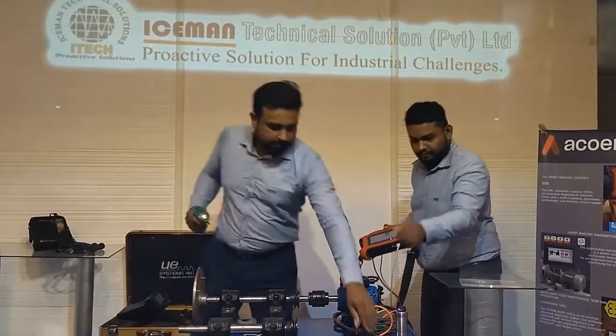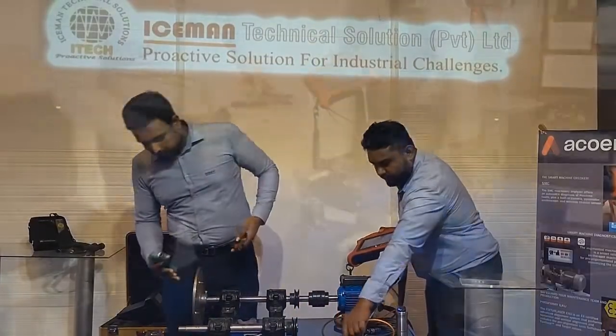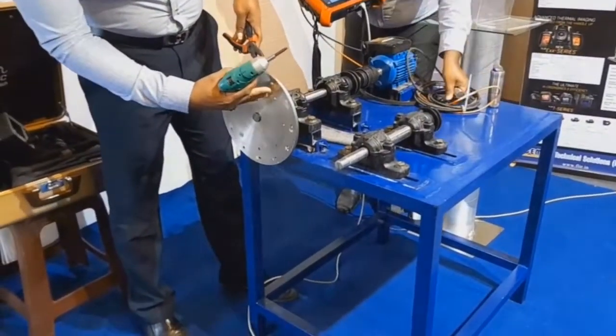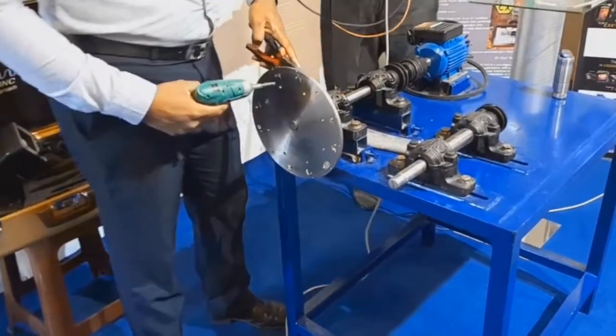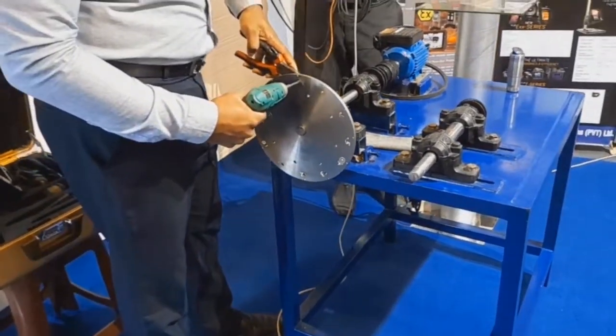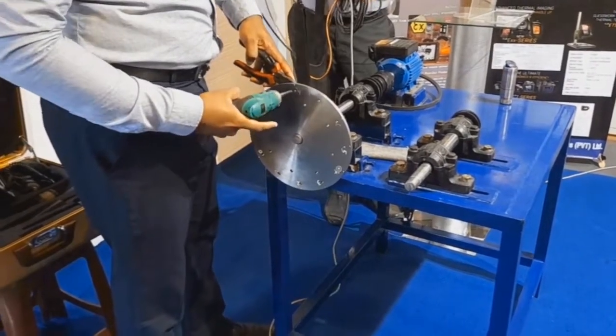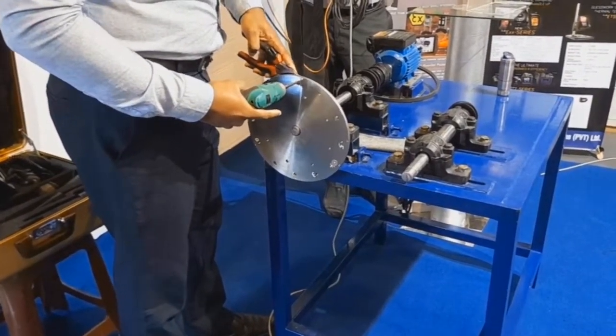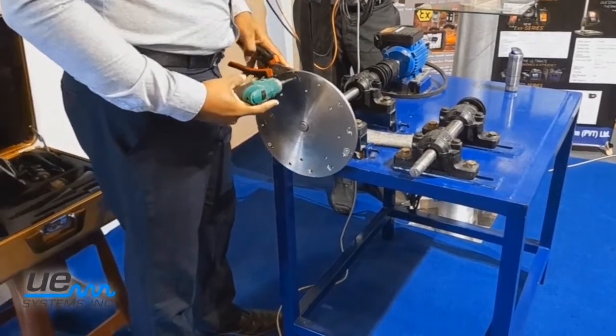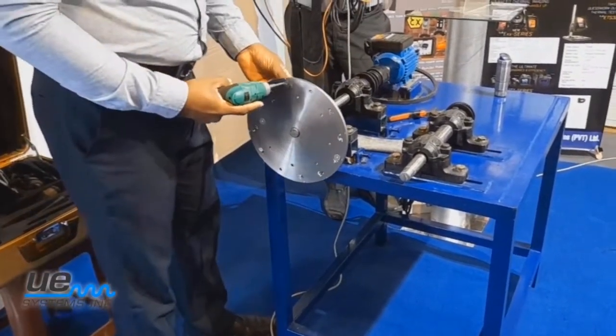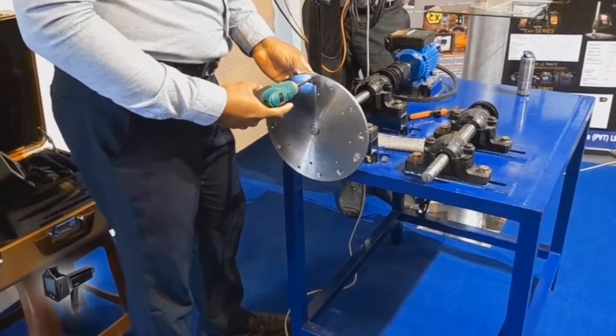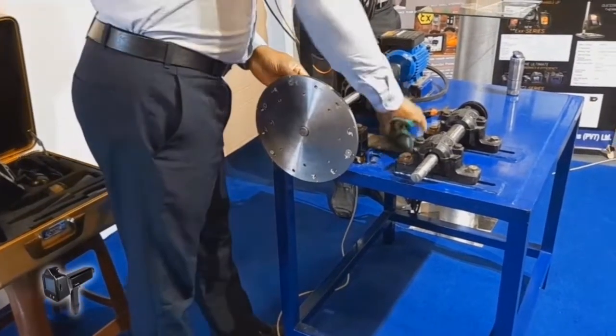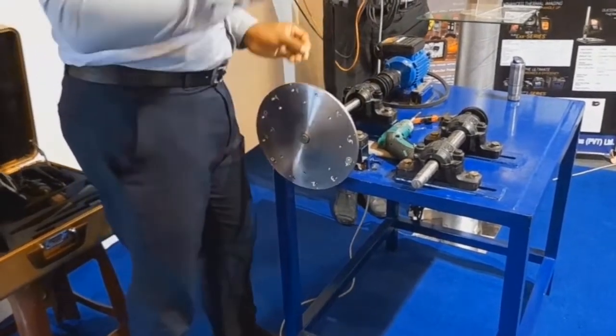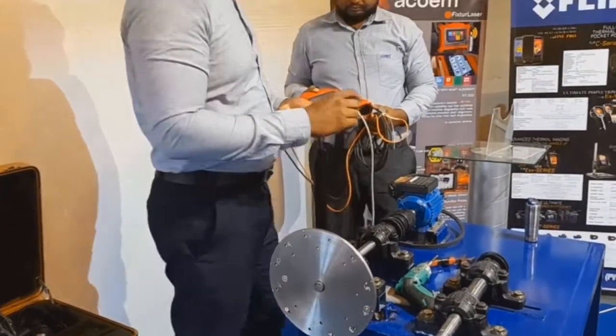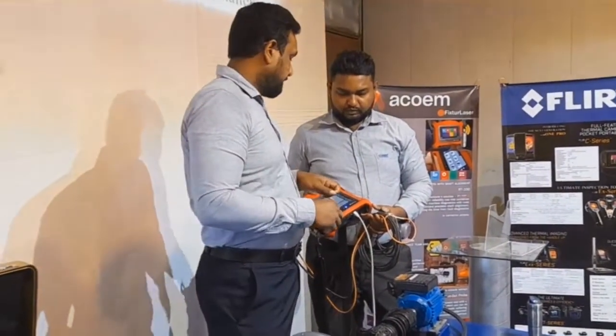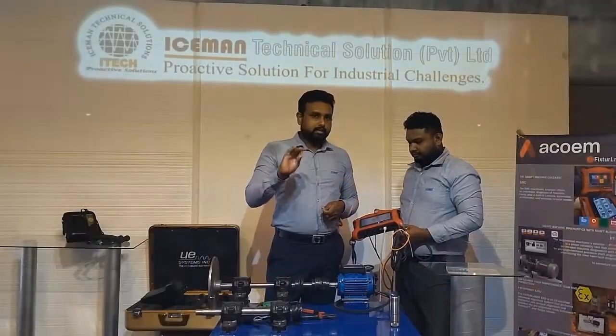Balancing weight means to reduce the vibration from this. To add the balancing weight, first we want to remove the trial weight. Now we remove the trial weight. The weight of this is 4 grams. The tool also gives the balancing weight as 3.92. It's nearest to 4.